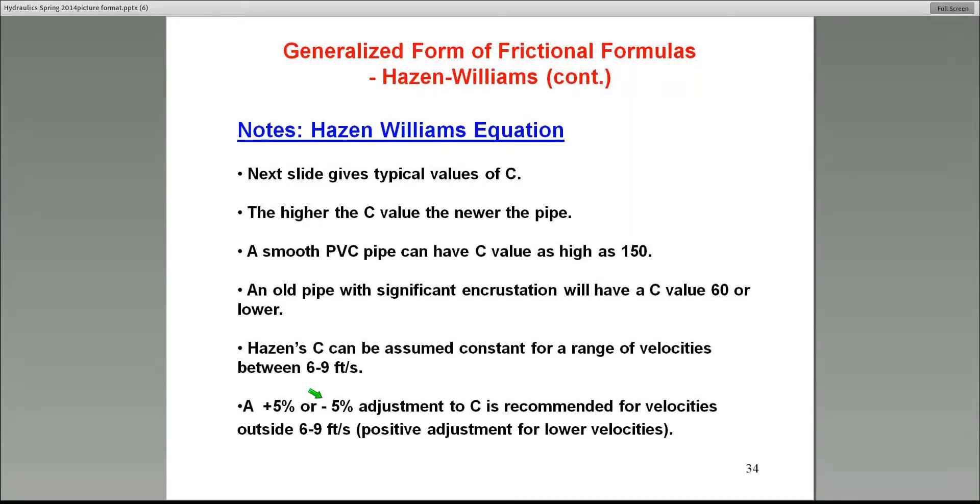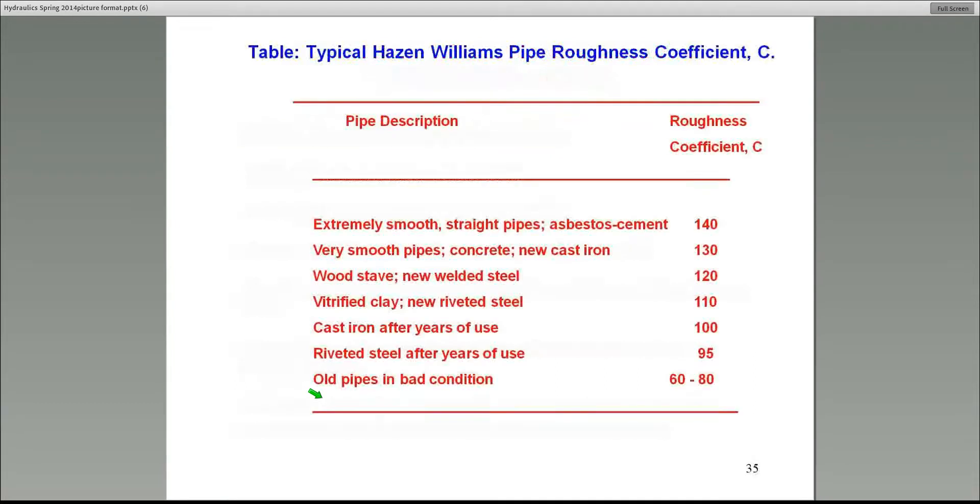But unlike the Darcy-Weisbach equation, you don't have the trial and error to deal with in this situation. Here are the typical C values in this table. Again, a cast-iron pipe, for example, right here. You've got a C of 130. A steel pipe has a C of 120. So, you can consult this table from the description of the problem, select your C value.